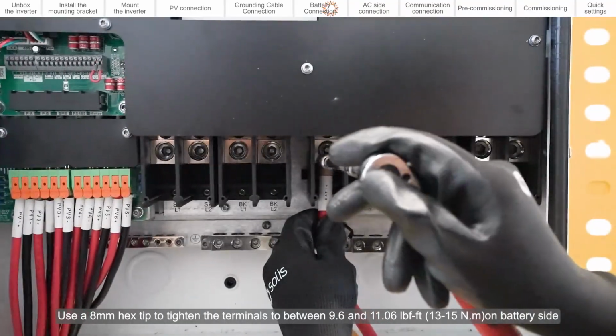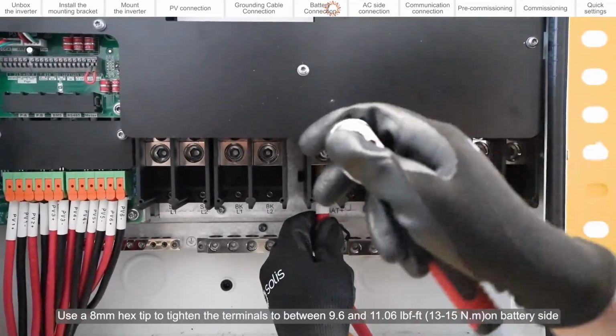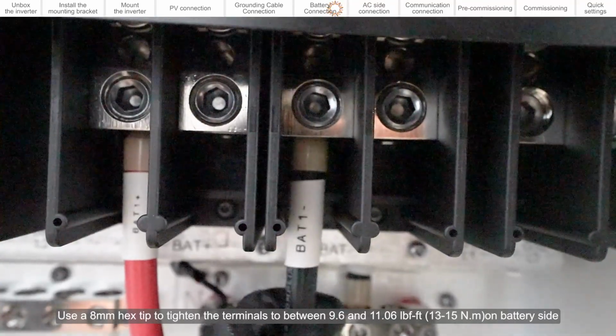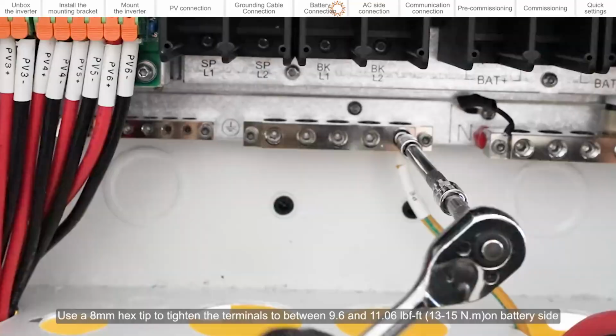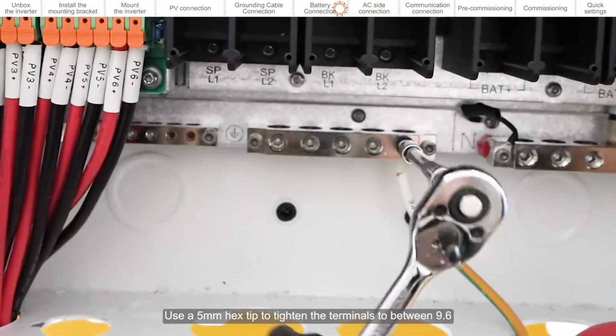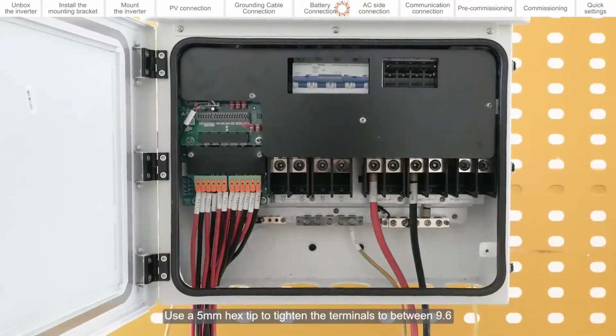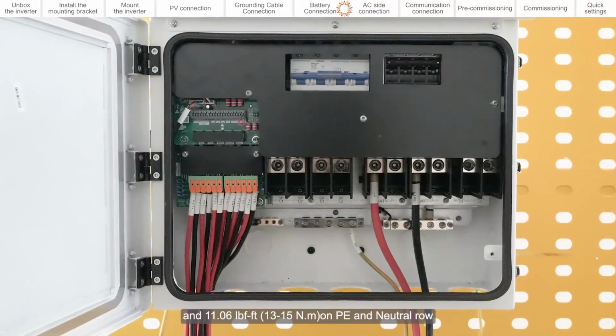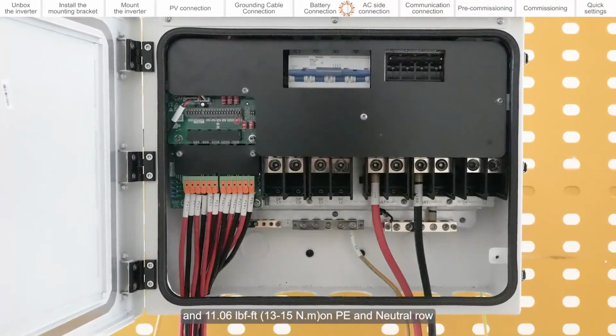Use an 8mm hex tip to tighten the terminals to between 9.6 and 11.06 lb-ft on the battery side. Use a 5mm hex tip to tighten the terminals to between 9.6 and 11.06 lb-ft on the PE and neutral row.